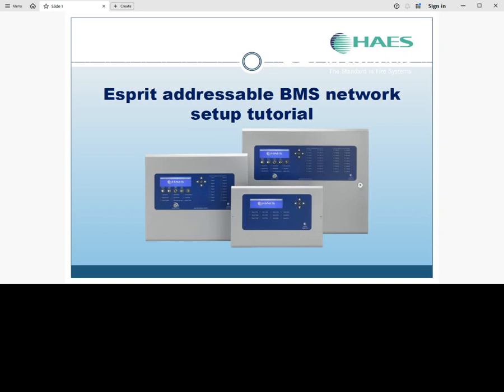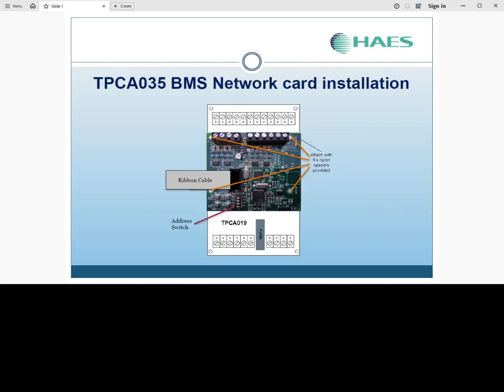In this video, we will be looking at the installation and setup of the BMS network card. The TPC A035 BMS network card should be fitted over the top of the TPC A019 PSU card inside the panel. The existing ribbon cable plugging into the TPC A019 PSU card should be removed and the card fitted using the 4 nylon standoffs provided. At the bottom of the network card are the 4 address switches as shown. Once installed, the ribbon cable from the display is then plugged directly into the network card as shown below.